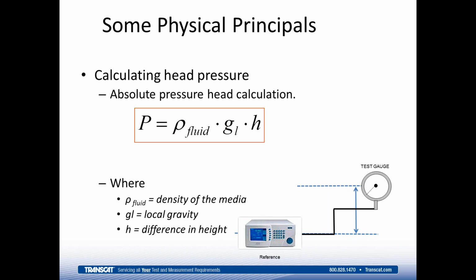That phenomenon is what's referred to as a reference head or head pressure. And it exists in all fluids, whether it be gas or liquid. And it's calculated as the density of the fluid times the local acceleration of gravity times the height in question.